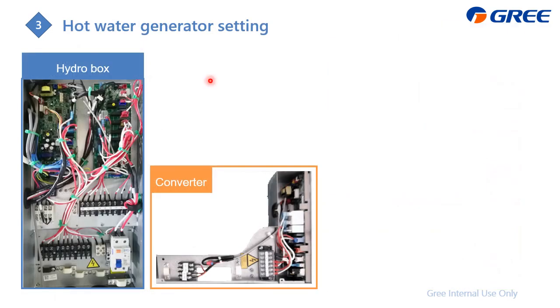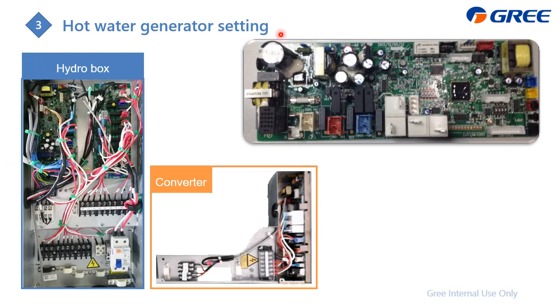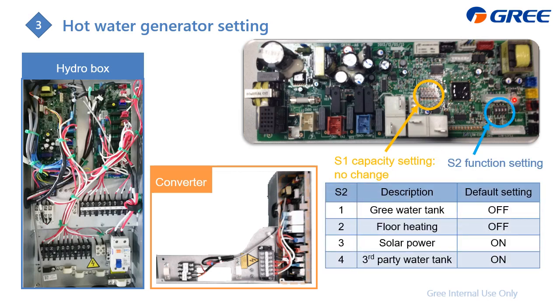According to your actual requirement, you need to tell the system which function you activate and which function you would not like, which is to deactivate. And here is how to do the setting, which is also on the PCB. For the hydrobox it is located here, this one, and for the converter, it is this one. There are two switches. This one, S1, is for capacity. Also keep it unchanged. This one is the function to tell the system which function you like and which you don't want. And just follow this table to activate this switch, okay.